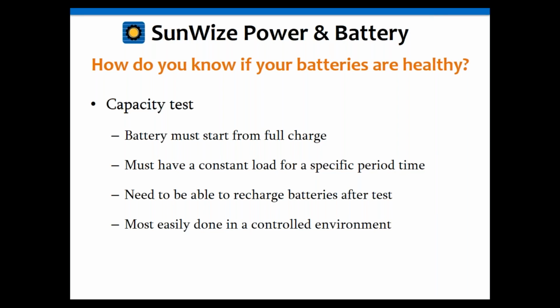Where it is, to figure out when it needs to be replaced or not. A general rule of thumb is if your battery is only at 80% capacity, so as an example, if you've got a 100 amp hour battery when it's brand new and now it's only holding 80% of its capacity, then it might be time to replace that battery. But again, the only way to confirm that is with the capacity test, really.